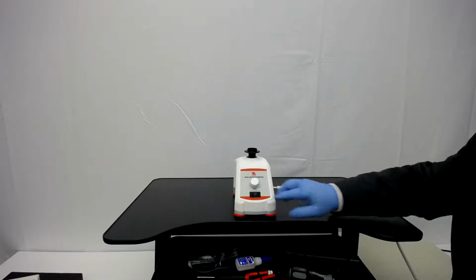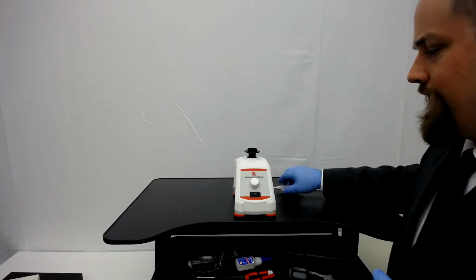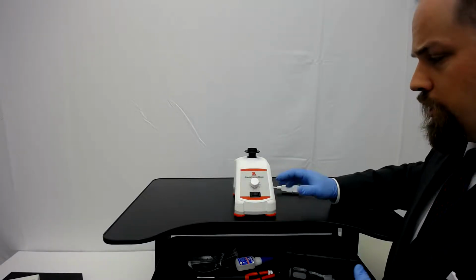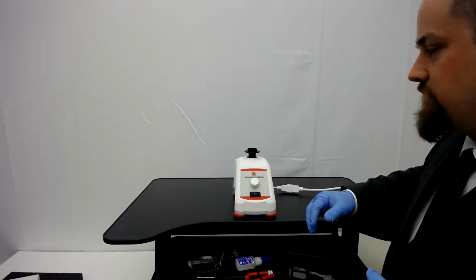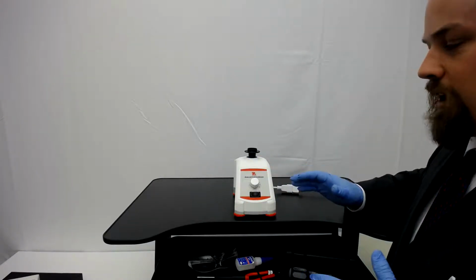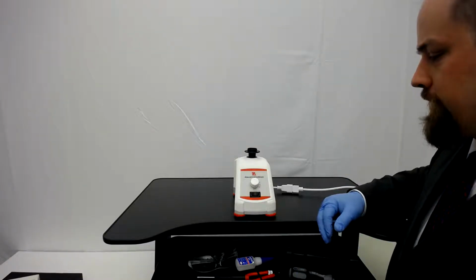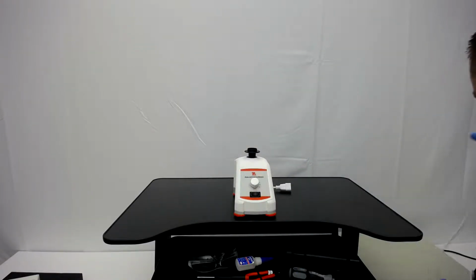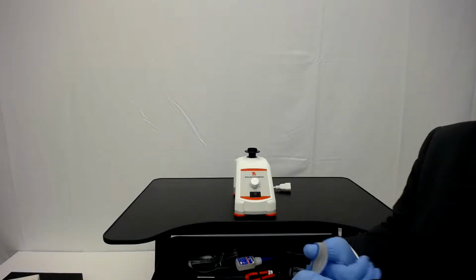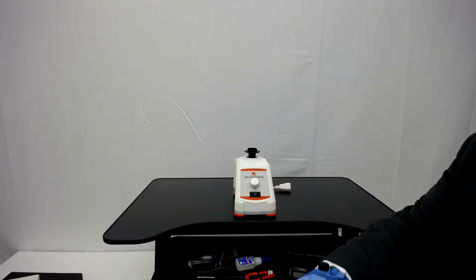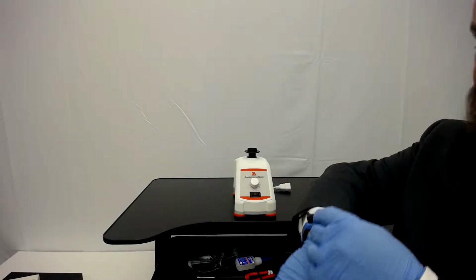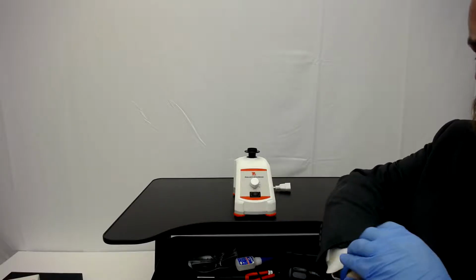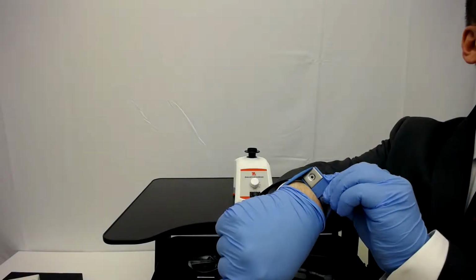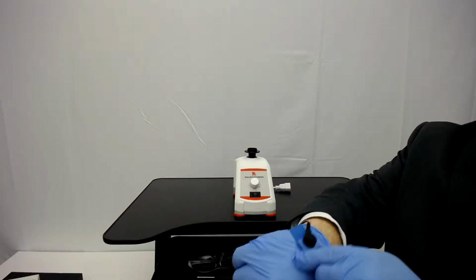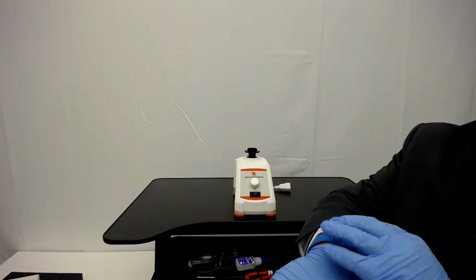Before starting on any of the units, check it for scratches, check it for any aesthetic issues, look it over. Always a good idea to take pictures of it before you start the repair. Document how the customer brought it back to you. All right, we're going to unplug this unit. We are going to put on the ESD protection. As I put on this ESD protection, note that I am getting the metal contact here in contact with my skin. It's not over clothing. It's not over my gloves. It's in contact with my skin.